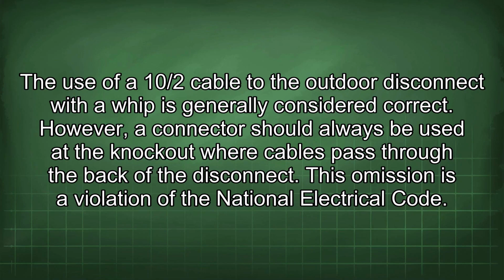The use of a 10/2 cable to the outdoor disconnect with a whip is generally considered correct. However, a connector should always be used at the knockout where cables pass through the back of the disconnect. This omission is a violation of the National Electrical Code.